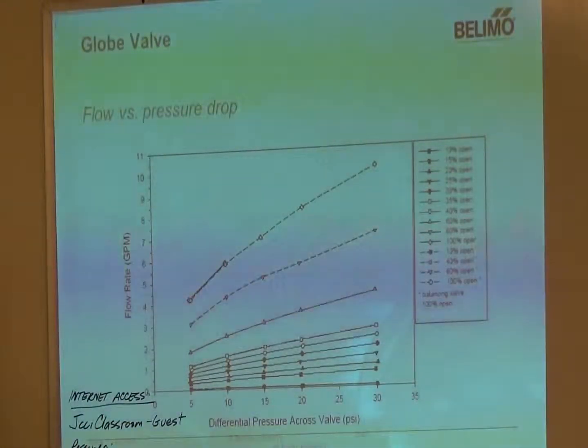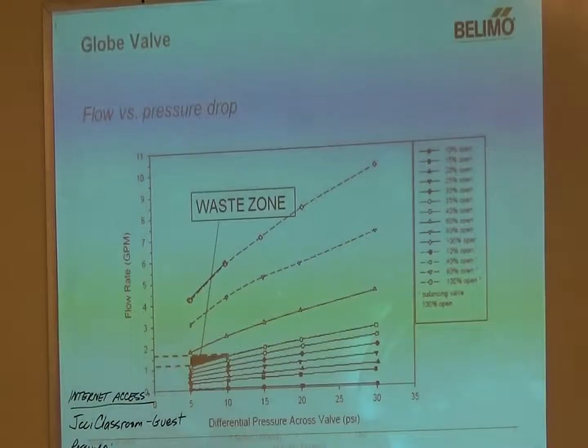This graph here is from an independent study we had done at a place called the Iowa Energy Center, part of Iowa State University. We had this done when we first brought out our PICCV, our smaller pressure independent valves. This is looking at a pressure dependent valve, and we're going to look at what happens at different differential pressures across the valve. Typical 5-pound differential, we're at maybe 1.2 GPM. Bump that up to a 10 psi differential. You can see our flow in our pressure dependent valve goes up to maybe 1.7. So you're talking half a GPM difference. And that's what this little waste zone, as we call it, represents.